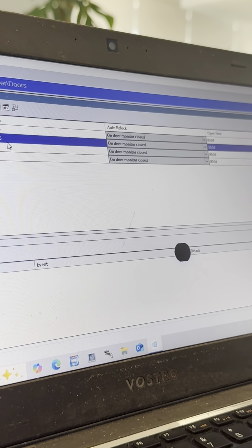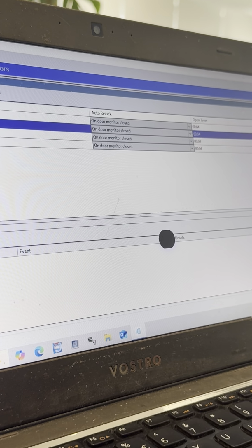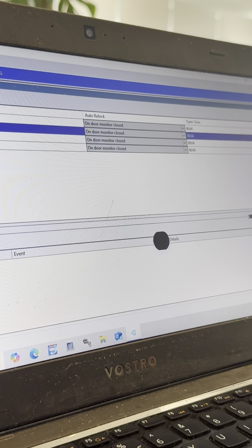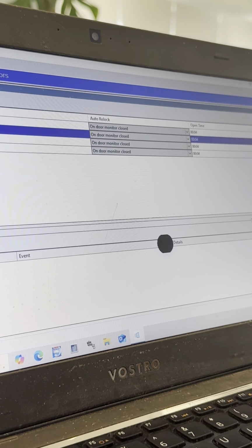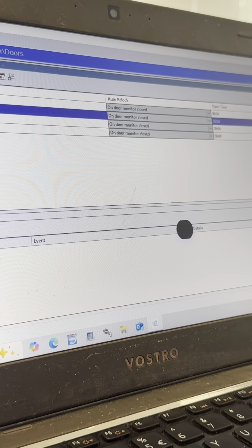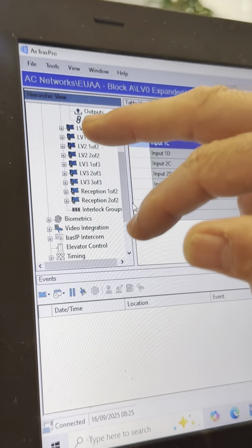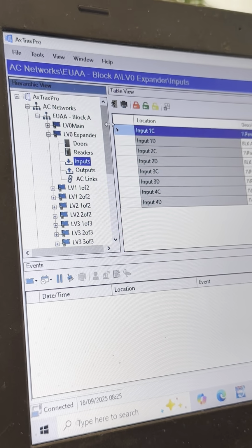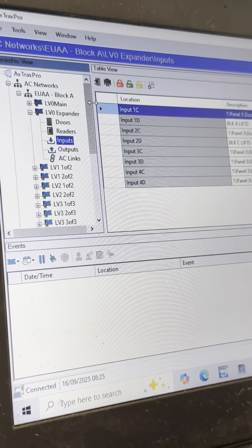One question for the magnet. We do the connection for the door contact like normally close, because I think it's better connected on normally open. Yes, but we already programmed it that way. The reason is the default settings are like that. Rather than changing every single input, you've got 4 inputs for every expander. You've got, I don't know how many expanders we've got there. 1, 2, 3, 4, 5, 6, 7, 8, 9, 10, 11, plus 12, because it'll be that times 4. You're saying 48. So you'd have to change it 48 times.